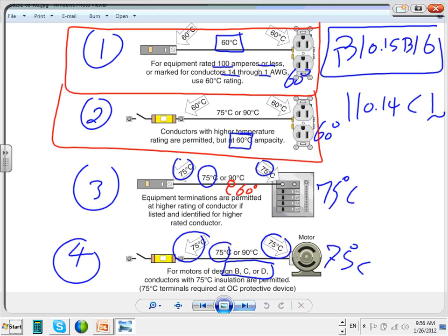Your default is number 1, right? Your default is number 1, 100 amps or less, or these conductors are 60-degree. Anything higher than 100 amps or more than number 1 is 75. Make sense? That's what we've been using, the 75-degree column. Any question, guys, about this? Yes, Chris, you had something.